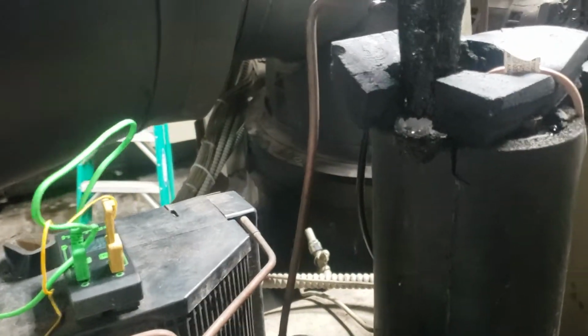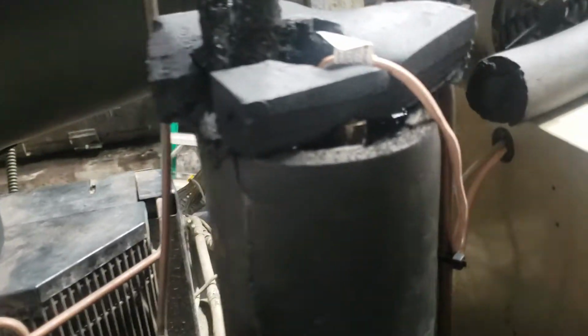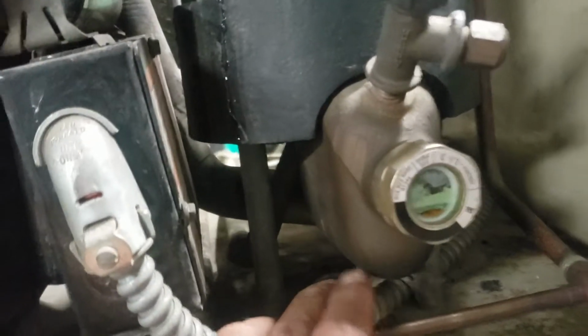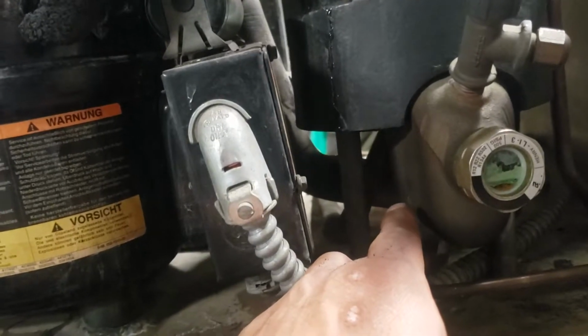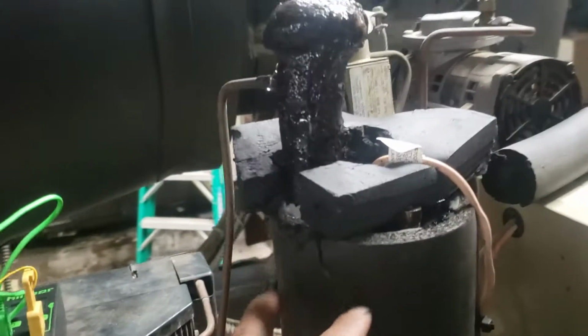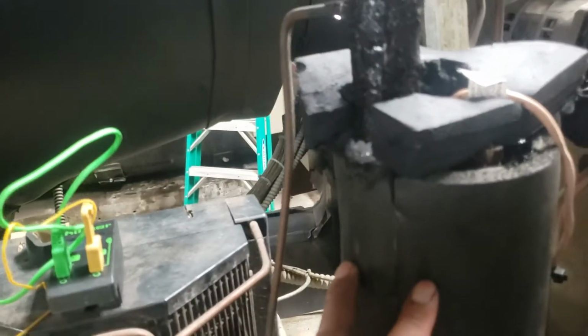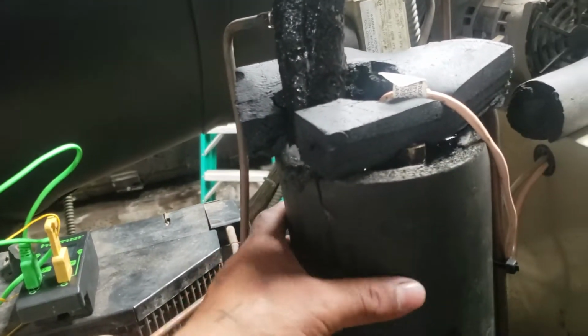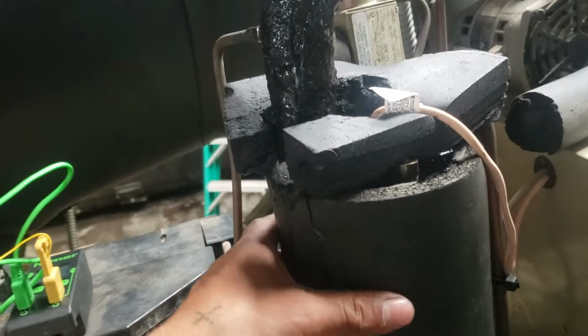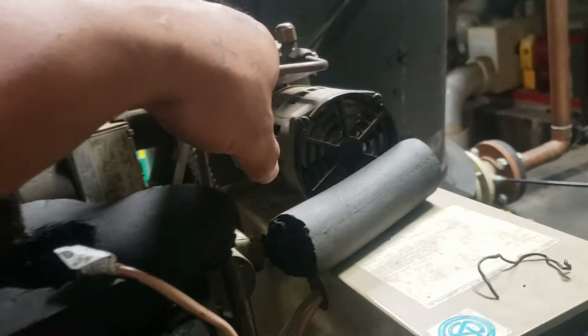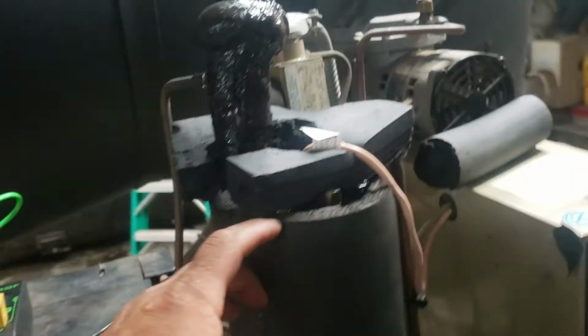So right here, underneath this Purge tank, you've got your vapor refrigerant coming from the condenser of the chiller. This is at a much lower temperature, so it attracts that vapor. It attracts that vapor, and that's what keeps the evaporator at a high enough temperature where it won't kick out the pump.